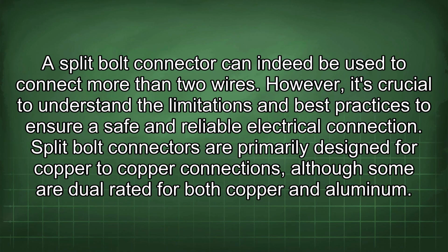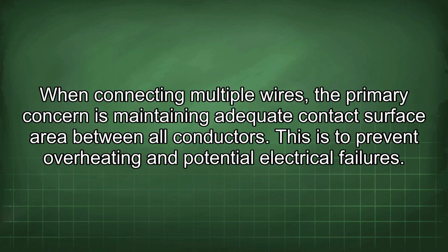A split bolt connector can indeed be used to connect more than two wires. However, it's crucial to understand the limitations and best practices to ensure a safe and reliable electrical connection. Split bolt connectors are primarily designed for copper-to-copper connections, although some are dual-rated for both copper and aluminum. When connecting multiple wires, the primary concern is maintaining adequate contact surface area between all conductors. This is to prevent overheating and potential electrical failures.